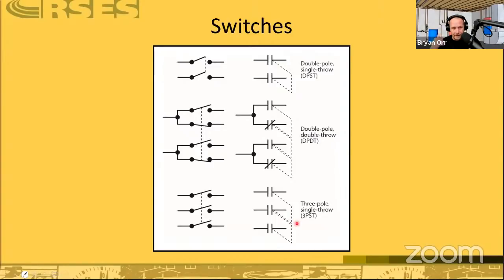As an aside, we can use what's called a plus-one contactor, where you have a contactor with one set of contacts, but the other side is just a straight pole, so it's really only a single pole contactor. We can use that in residential, but in 3-phase you always have to break all 3, because if you don't, that motor will still try to run.